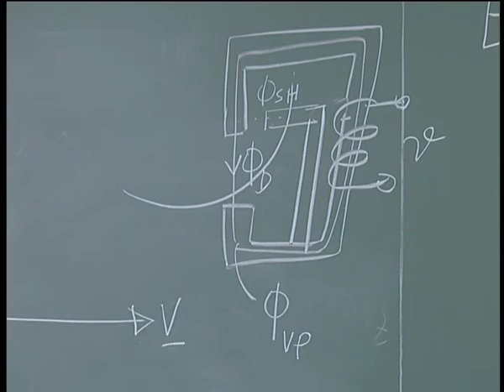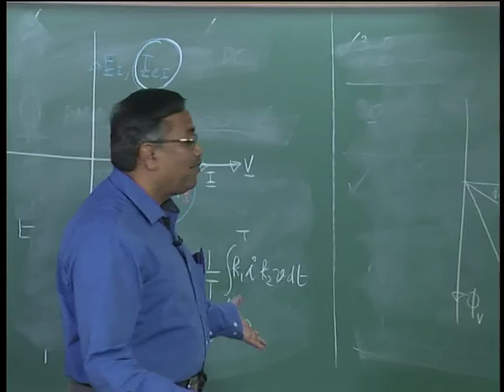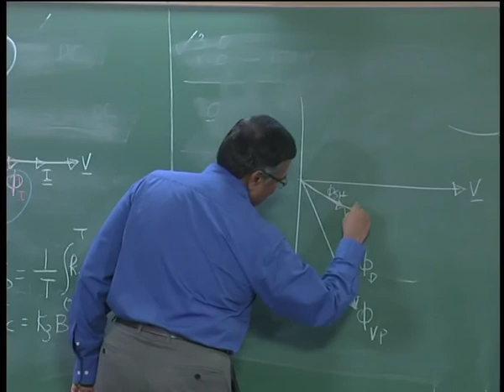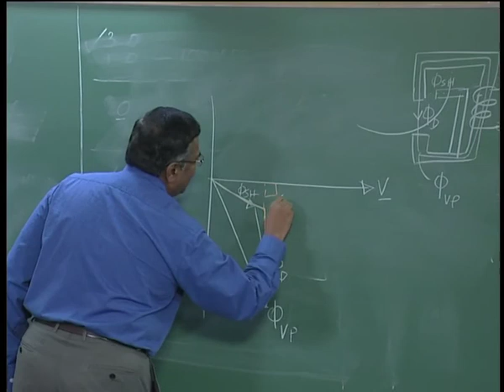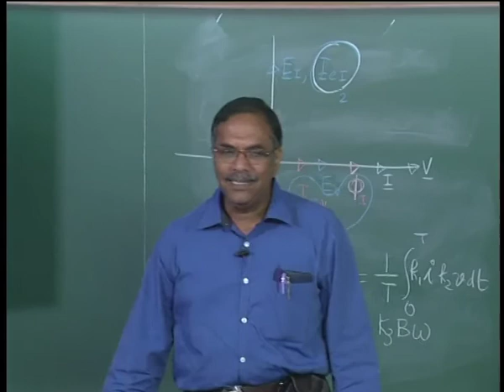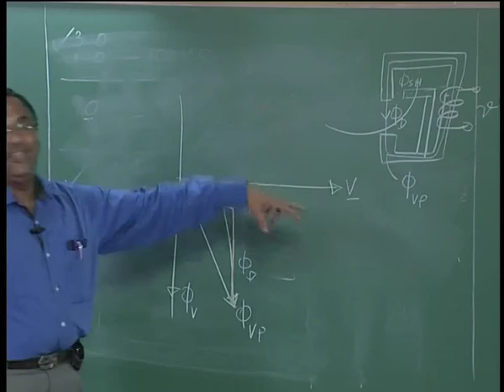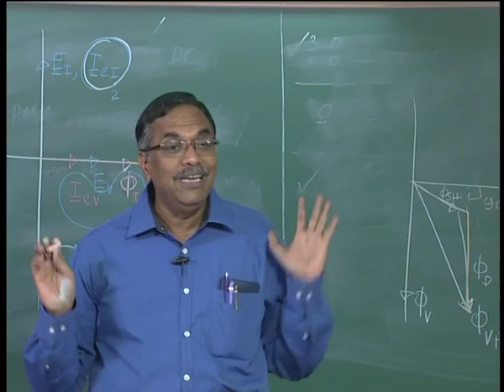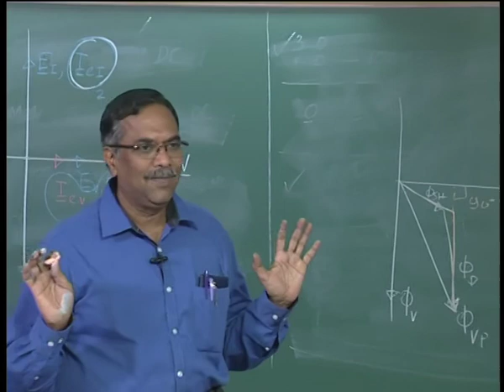Now if I look at phi Vp, it splits into two components: one is the shunt flux, and the other is the disk flux. These two must add up to the total flux produced by the voltage coil. Now I can adjust the shunt flux such that the flux through the disk is exactly 90 degrees relative to the voltage. In this process I may not have the full voltage flux going through the disk, but I will have a part of it going to the disk, while ensuring 90 degrees between the applied voltage and the flux.